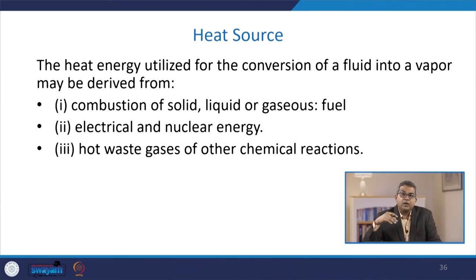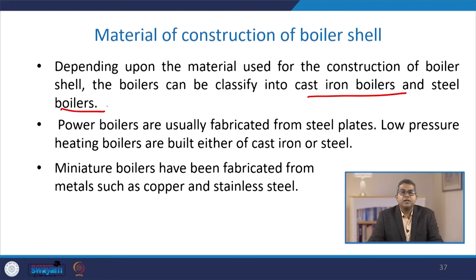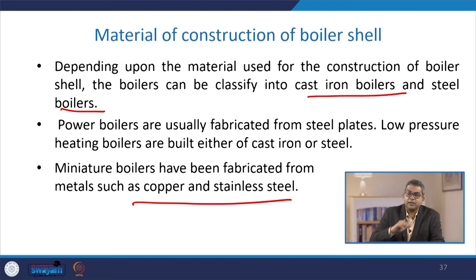Another classification can be given based on heat source. Heat energy utilized for conversion of fluid into vapor can be derived from combustion of solid, liquid, or gaseous fuel, or from electrical and nuclear sources, or from hot waste gases of exothermic chemical reactions. Another classification is based on material of construction of the boiler shell. Boilers can be classified as cast iron or steel boilers. Power boilers are usually fabricated from steel plates, while low pressure heating boilers are built from cast iron or steel. Miniature boilers have been fabricated from metals such as copper or stainless steel.